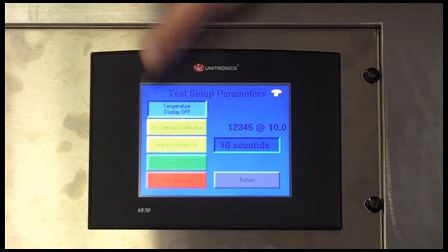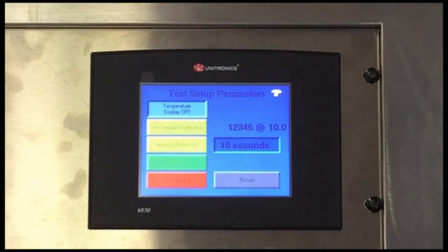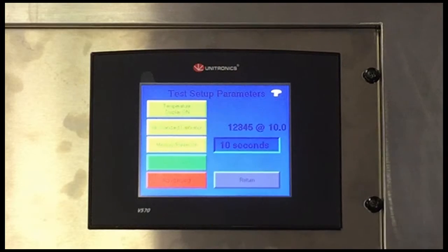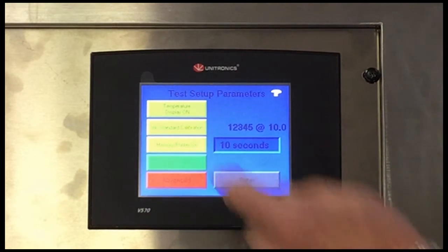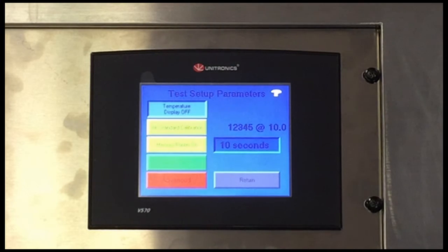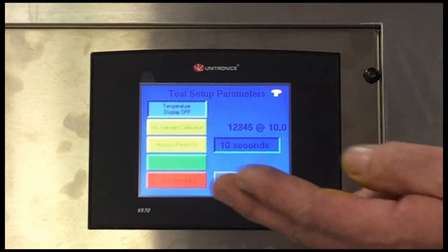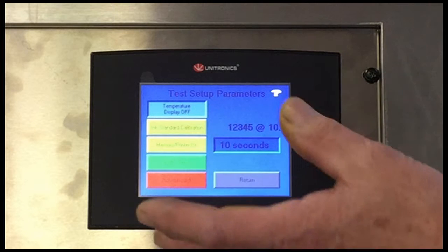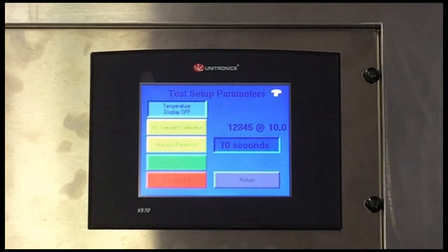We have a temperature display. On some of these models, we supply an external temperature sensor that measures the water bath temperature, and some of them we don't. So this button here allows us to turn that temperature display on or off. Obviously, if we don't have the display, we turn that off. If we do have the temperature sensor, then we can turn that on and a temperature display will appear on the test screen when we actually run the test.